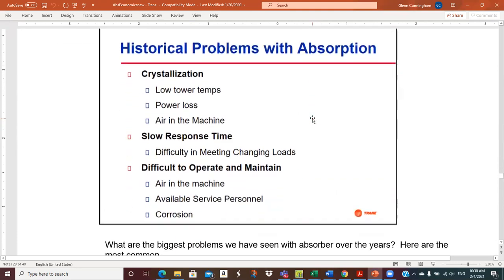Okay, historical problems. We've been through this. Crystallization, low cooling tower temps, power loss, air in the machine. We went through some of that. Slow response time. The old absorbers had difficulty in meeting changes in load. So, a big cloud, the front would blow through and the cooling load would go down, and they just didn't react very quickly. And then difficult to operate and maintain the machine: air, purging, service personnel, corrosion issues.